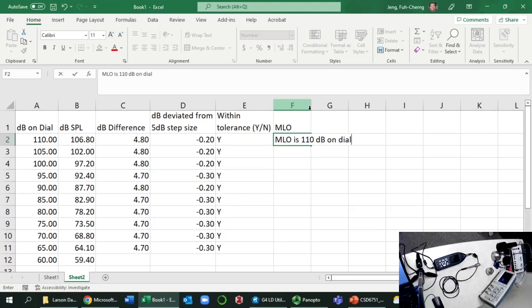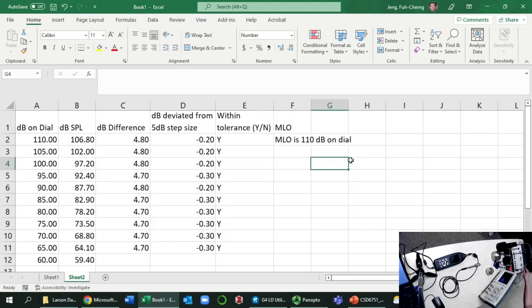Okay, so this is fairly common for an audiometer. Have you wondered how come when I turn it to 110 I cannot go any further? Am I making sense? Because when a professional calibrator came in and tested up to 115, they found it violates the linearity. They disabled it. Am I making sense? So that's the reason I have linearity within all the range I can use, and that's the reason when I switch to a different frequency, I can only go...